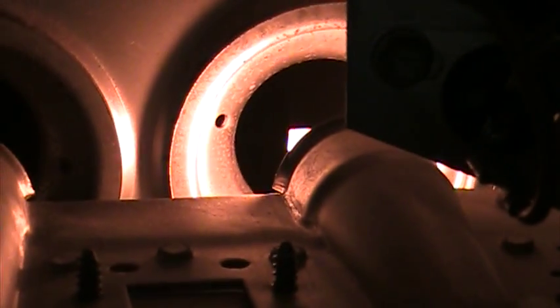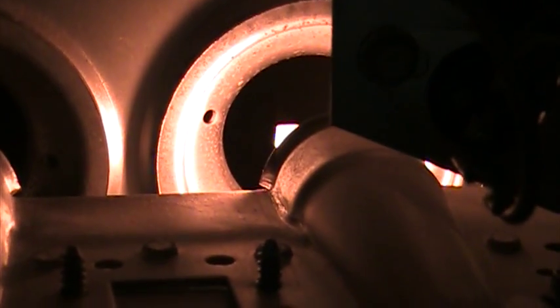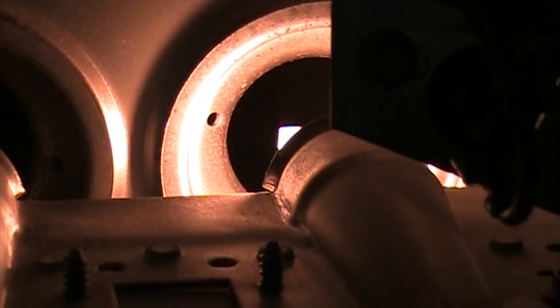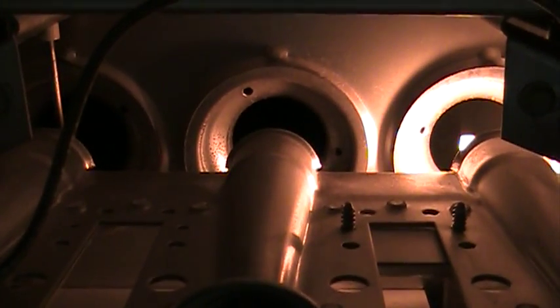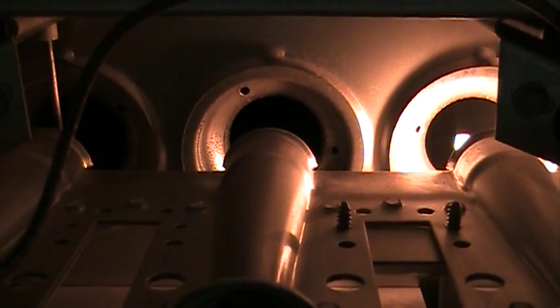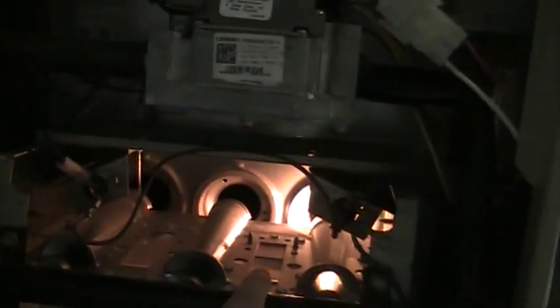There she goes. All right. So igniter's on. Draft inducer came on. That click was the gas valve opening. And the burners just lit. Those are the burners.